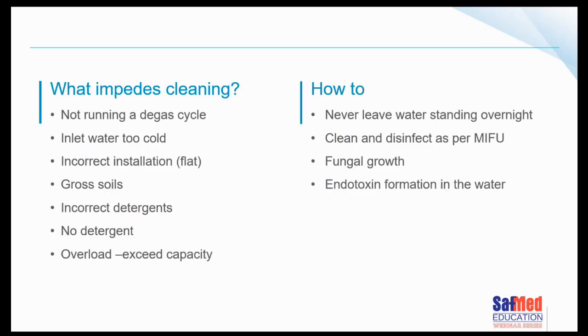So remember now that there's certain things that can impede the cleaning efficacy, and that will include not running a degas cycle. If the inlet water is too cold, of course, depending on the make and the model, again on installation, the manufacturer will stipulate that you need incoming water at a certain temperature. A lot of the machines have the ability to warm the water slightly or keep it warm, but they don't necessarily have the ability to warm it from cold.